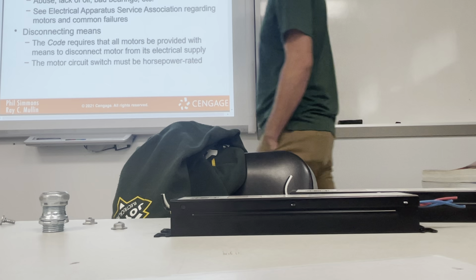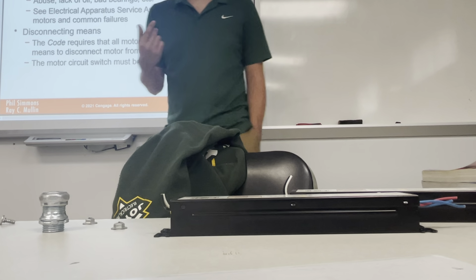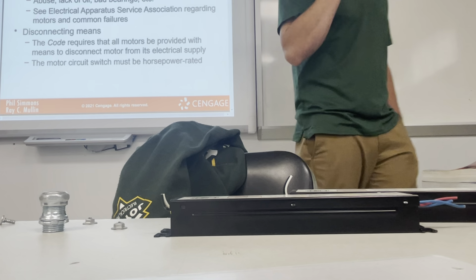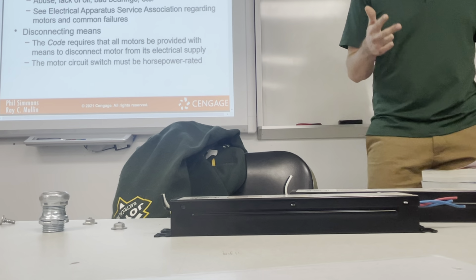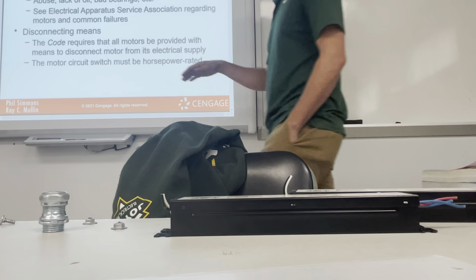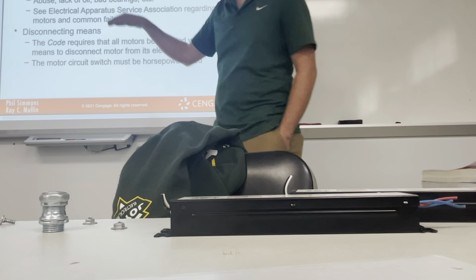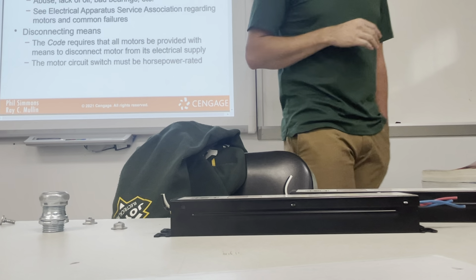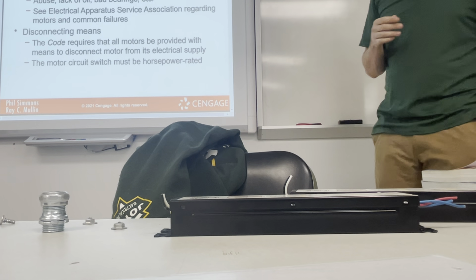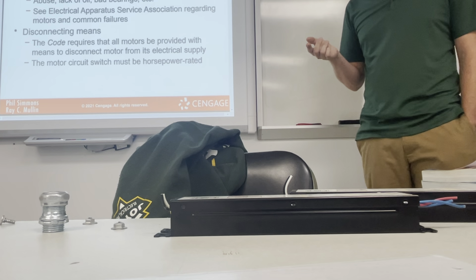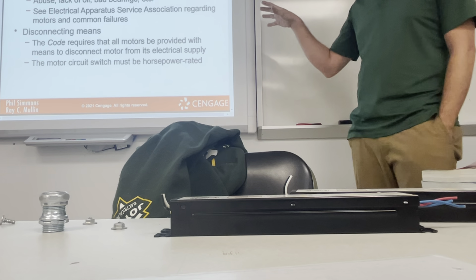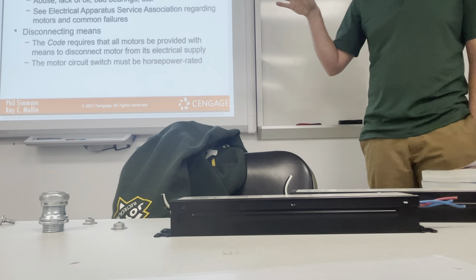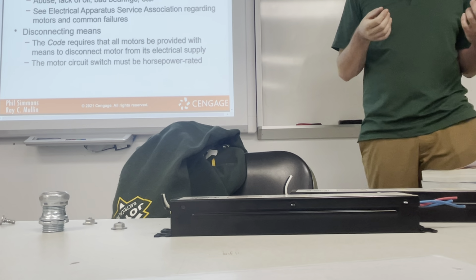All right, so yeah, motor failures are usually not because of the electrician. It's usually not because of the overload. It's usually not because of electrical current surges, weird things. It's always abuse, lack of oil, bad bearings. You're just getting the tar beaten out of that motor. As you'll find out in motor control, there is a way that we balance these with lasers. Yeah, because it's all shaft alignment.